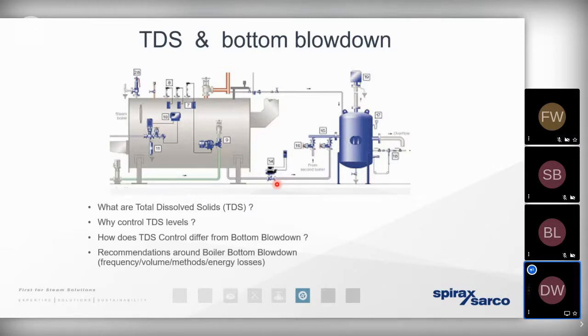So typically we address the TDS by taking a sample from the side of the boiler. We'll put conductivity probes across it. If and when it reaches a high conductivity, that's an indication that we've got a high total dissolved solid content in parts per million. We dump a certain mass of that high TDS boiler water to waste, and the level control probes then call for the same mass of cold water for us to bring the boiler up to the correct operating level again. But again, if we blow down too much, then we've got a significant inefficiency from an energy perspective. If we blow down too little, we're at risk that we're going to get steam contamination and very wet, sticky steam with very little energy in it.